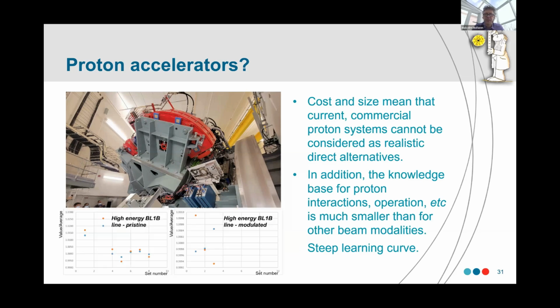And in terms of performance, this is some data that we acquired with our calorimetry at a proton beam at TRIUMF in Canada. And you see that with a modulated spread out beam over a short period, we're getting pretty good performance. So that's nice. But on the left-hand side, the measurements with a pristine Bragg peak, the first 2 points were one day, the second were another day, and we're seeing significant variations. So output and energy again become an issue for proton devices. This is not comprehensive data or saying all of them are variable at this level, but it just raises that we don't have at the moment the same level of confidence in these kinds of devices.